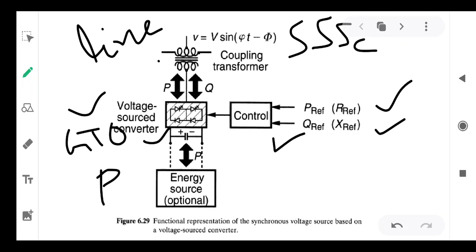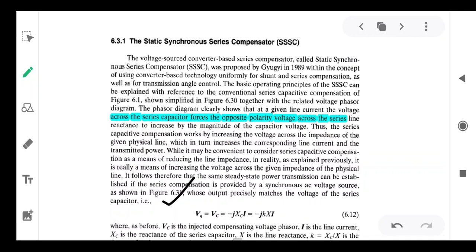Now, in a nutshell, this is the SSC. SSC is nothing but voltage source converter connected in series with the transmission line. Static synchronous series compensator, SSC. The voltage injected with the SSC is given by Vq equal to Vc, that is equivalent to minus jXc into I. Xc is the variable impedance type compensator or series capacitor, whereas in SSC we won't use capacitor, but we will use VSC in order to supply the required reactive power to the system, either it is lagging or leading reactive power. In both the cases, we can use plus or minus VQ.